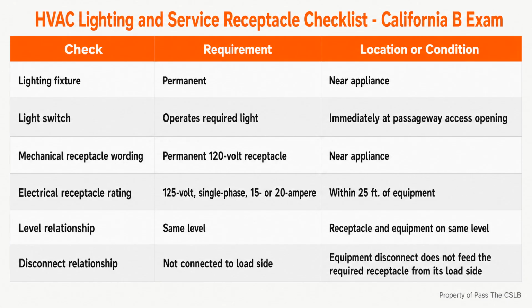I use a simple supervision sequence. First, confirm the equipment location and the actual service side. Second, confirm the largest component that may need to pass through the access. Third, lay out the opening, solid passage, and working platform without altering engineered framing. Fourth, reserve the route so ducts, pipes, braces, and wiring do not block it. Fifth, coordinate lighting, switching, and service power. Finally, inspect the complete route before concealment and again after the surrounding trades finish. That sequence is not a substitute for plans, manufacturer instructions, or the authority having jurisdiction. It is a practical way to find collisions while they are still cheap to correct.